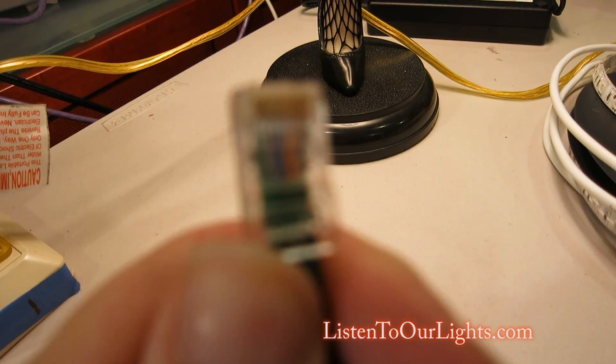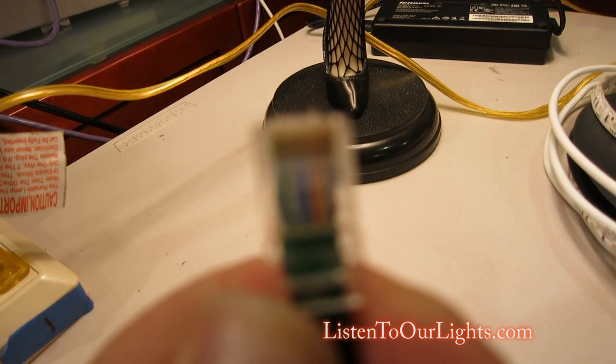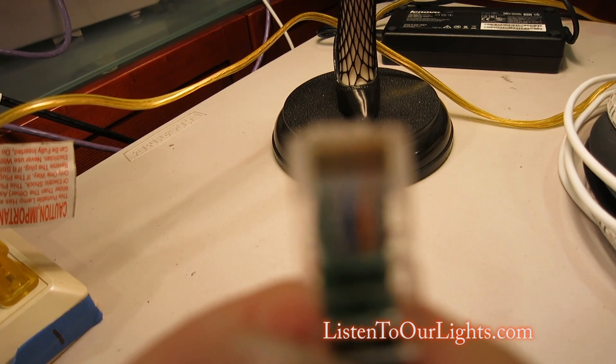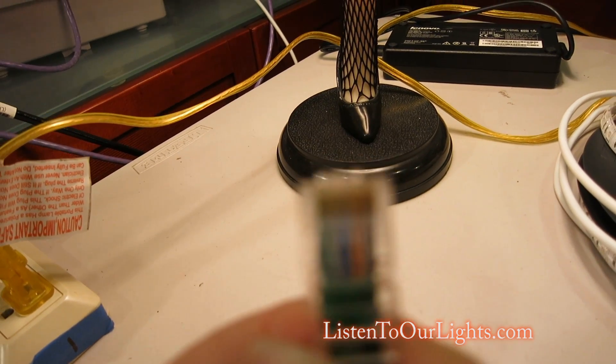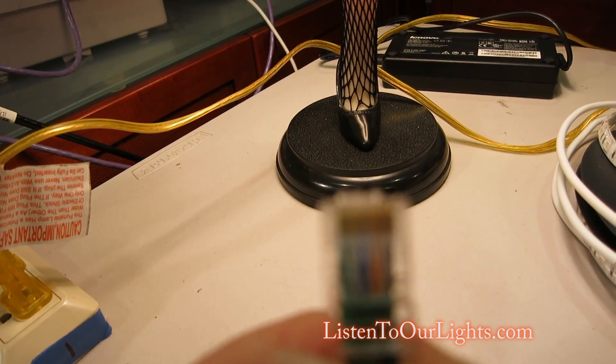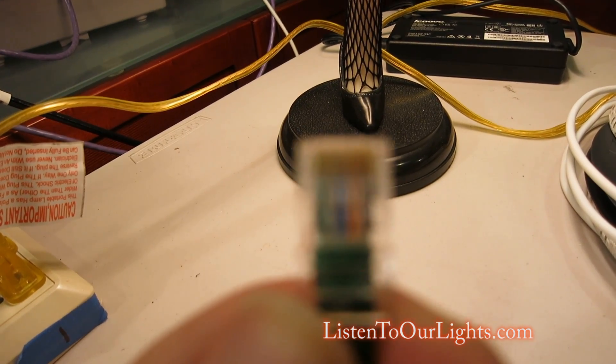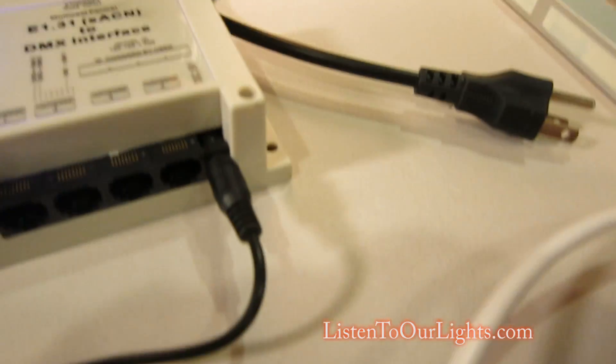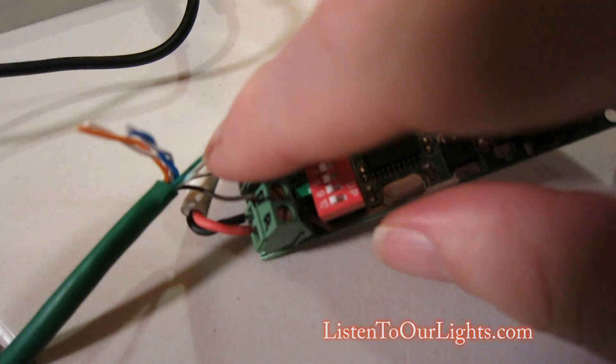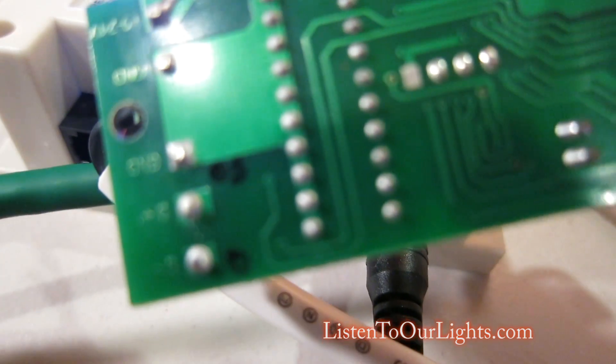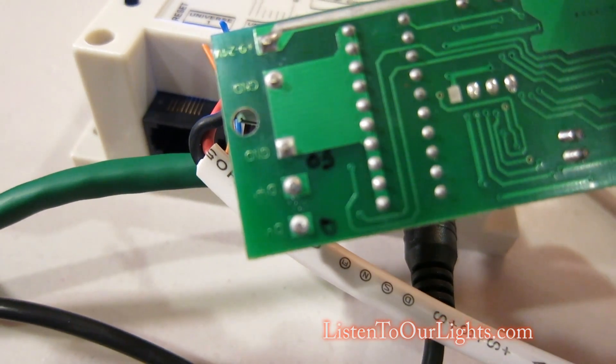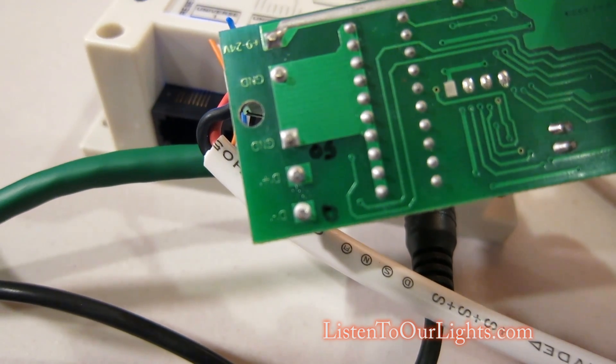So, on this side, on the left, pin 1 is the data plus, which is going to be my green stripe. The pin 2, the next one over, second one over from the left, is going to be data minus. That is the solid green. And then my brown stripe is my ground. Now I come over here to my controller. And I have the screw blocks for the DMX input right here. So, if we flip that over, we can see data plus, data minus, and ground. And so, I just wired them up exactly the same.